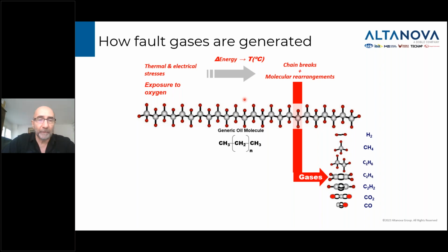So in a normal transformer, in normal operation, there will always be a certain level of hydrogen being dissolved into the oil. The level depends on the age of the oil, the load of the transformer, the mineral oil, and the design of that transformer. From our experience, we've seen transformers that in normal operation generate hydrogen levels of around 2 to 5 ppm, but we've also seen other transformers that generate hydrogen levels up to 500 ppm in normal operation. So you have the whole range of it that you see.